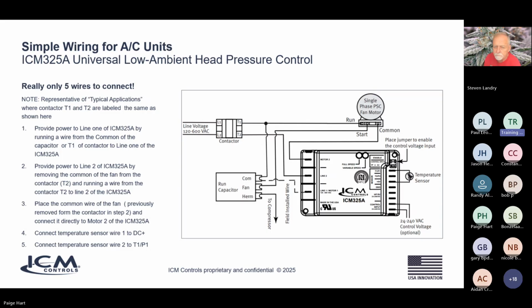So it's literally just line 1 and line 2, and you're just breaking that leg of power that would have normally went from line 2 back to the motor. You're just breaking that leg of power through the ICM and connecting the motor side to motor 2 and the line side to line 2.